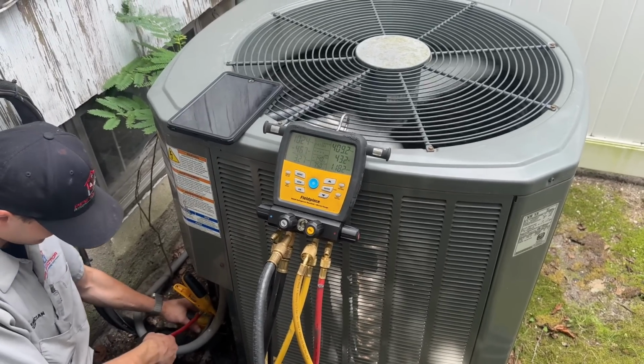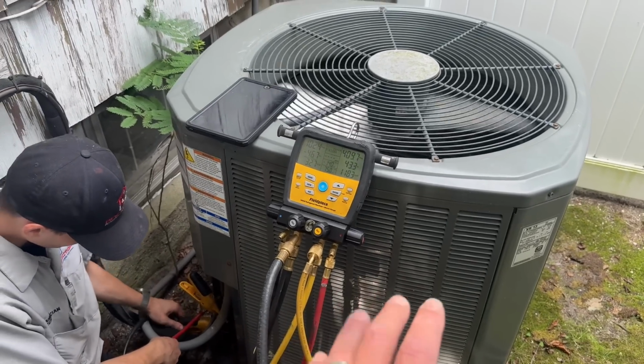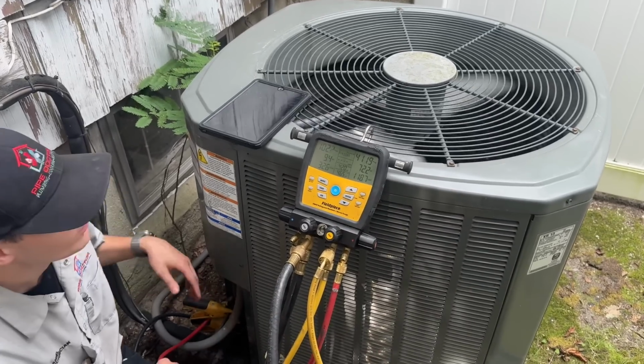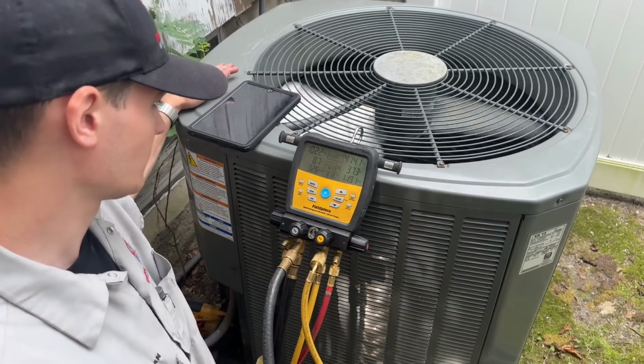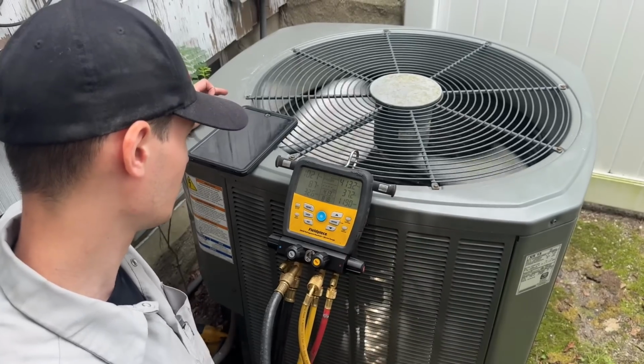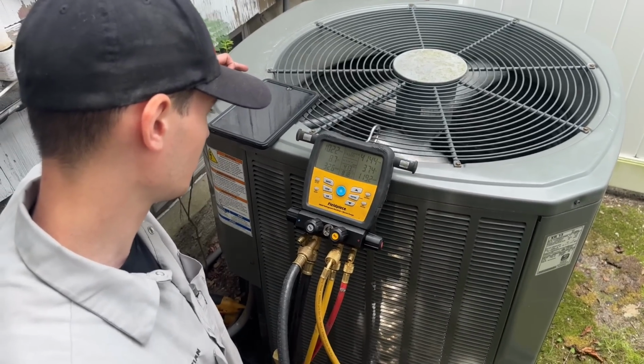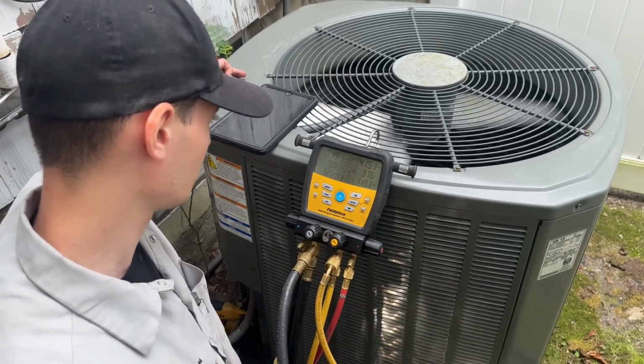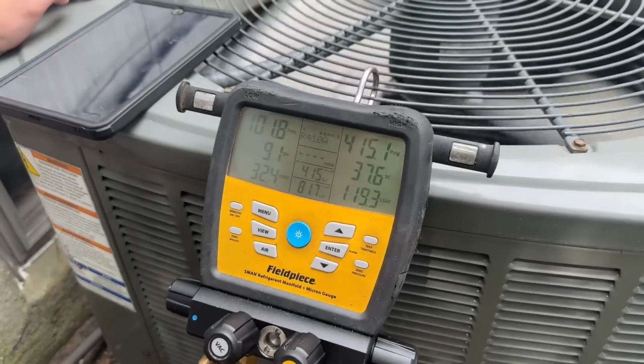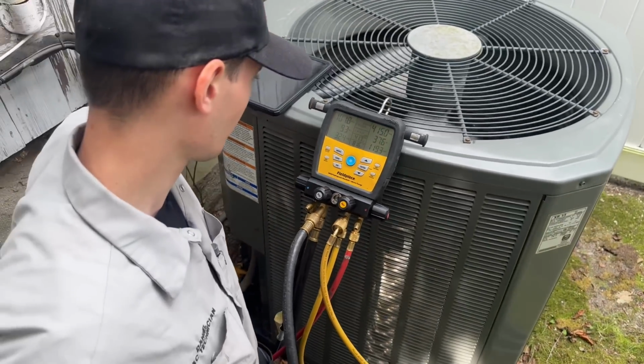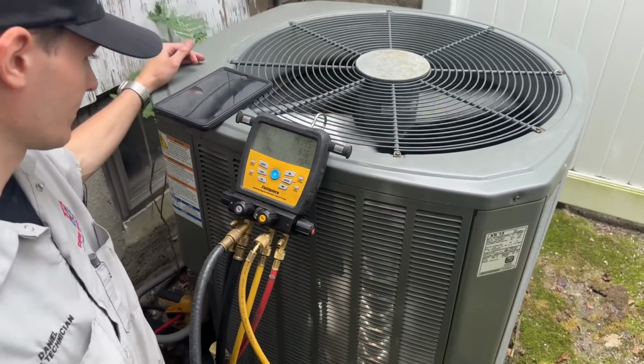I don't know. What I did do, though, was I was banging on the TXV last week when I was here, and the pressures did go down a little bit. So we may have to manually open up that TXV to let it pump down, but 415 PSI, that's just dangerous. And guess what? There is no filter dryer on the system.